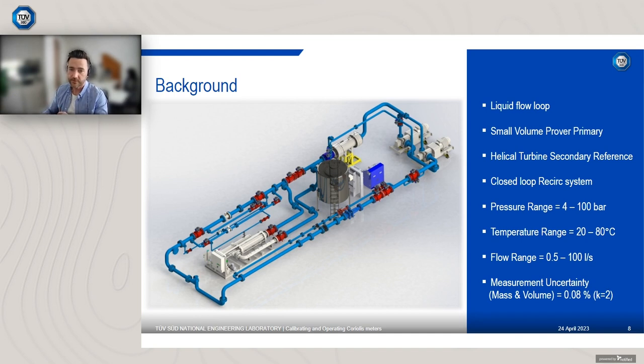The way that we would operate is you have the test section, the fluid would flow around through the prover, we would calibrate one of the master meters at the required condition, so let's say 10 bar, 50 degrees Celsius and 50 litres per second. We would then get the K factor for the turbine meter from the prover. We would then complete between 3 and 5 test points, repeat flow rate test points at that flow rate, temperature and pressure, and then we would do a post-prove again to ensure that the turbine meter hasn't shifted and is within our acceptability criteria. So overall, achieving uncertainty 0.08%.